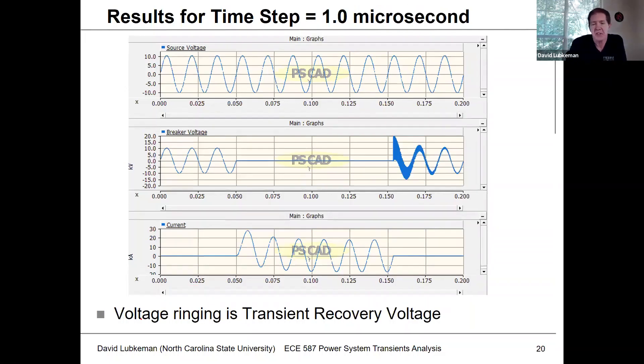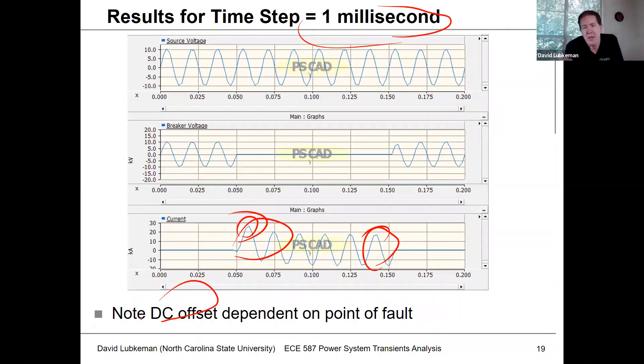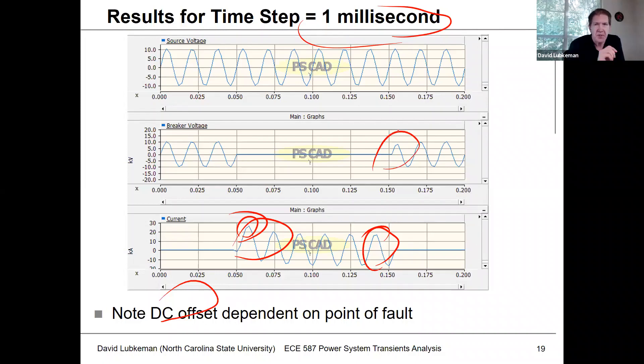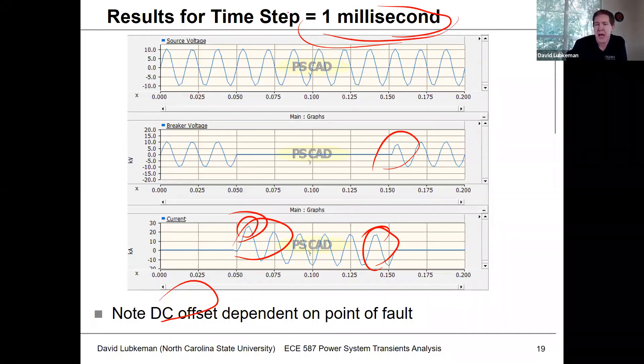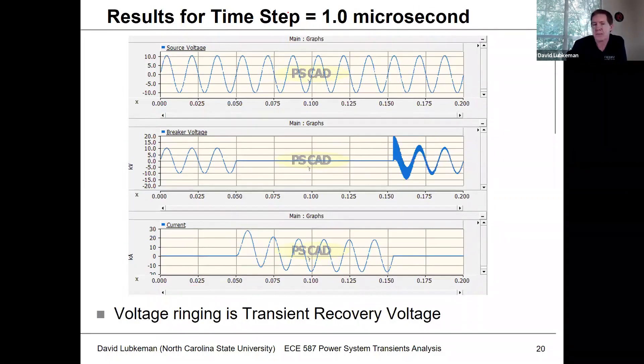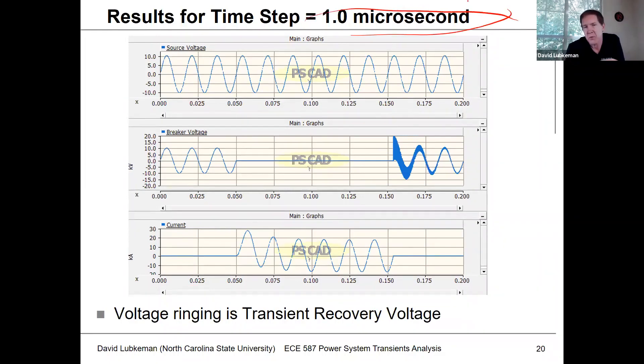The peak current depends on the ratio of reactance to resistance in the system. Depending on the nature of the source and when the fault occurs — what portion of the cycle — you'll get different peak currents. When the fault is cleared and you look at the voltage at one millisecond resolution, it looks like the voltage goes back to normal.